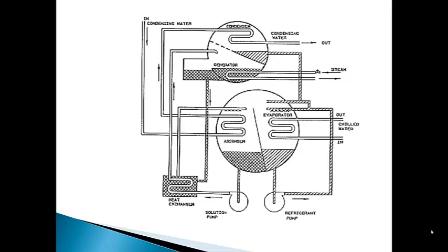Here is a schematic of a commercial absorption chiller. The lower vessel is divided by a wall that separates the evaporator section on the right from the absorber section on the left. The evaporator section contains a heat exchange coil that brings low-grade heat into the vessel, while the absorber section has a set of heat exchange coils that remove heat from the absorber. The 2 coils handle roughly the same amount of heat, that is, the latent heat of evaporation of the water vapor passing from the evaporator to the absorber.